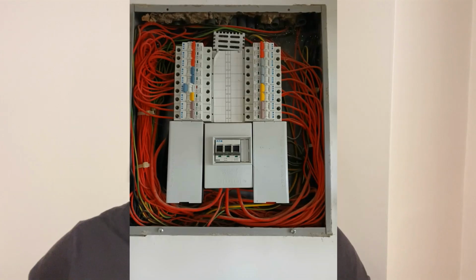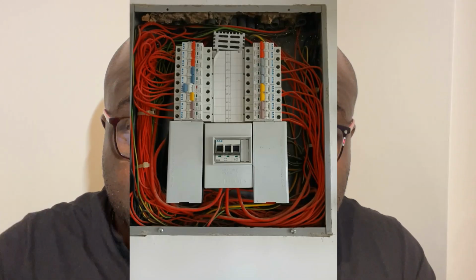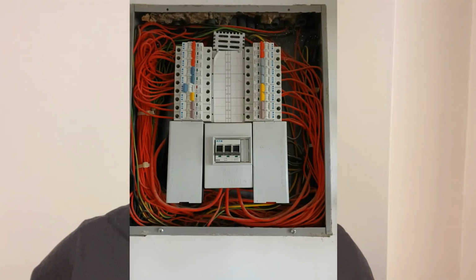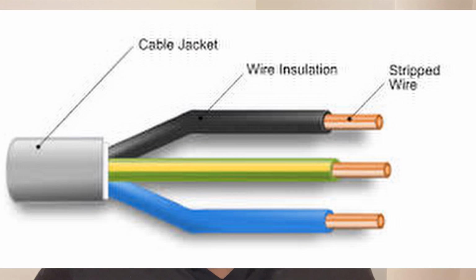Distribution boards are not a decoration. They are proper electrical centers. Common problems will occur when you have too many circuits on one bus bar. Heat is trapped in the sealed cabinets. When heat is trapped over time, it builds up, and then one day, God forbid, the worst happens. Heat buildup inside boards accelerates the insulation breakdown. The insulation is the material around the cable that protects the copper where the electricity is being conducted. When the insulation breaks down, then that copper, which is conducting the current and overheating, can touch something live and then can ignite. So this is the issue.